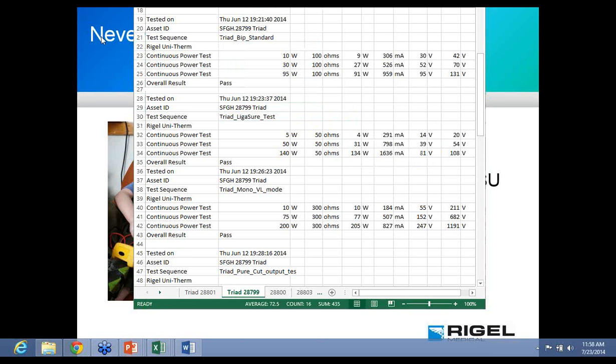So I have a question about the bipolar test - what's the specific load resistance? Very often it's 100, sometimes it's 50. You have to refer back to the manufacturer's guidelines. The ConMed Saber, which is a very popular device, uses a 50 ohm load for its test. The Covidien Valley Lab uses 100 ohms. You have to use manufacturer's guidelines for that.